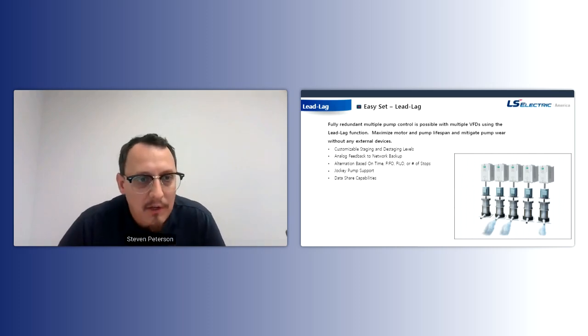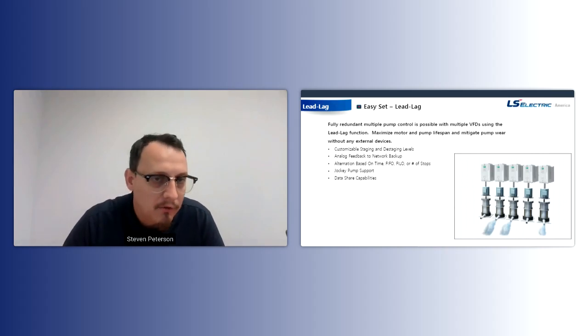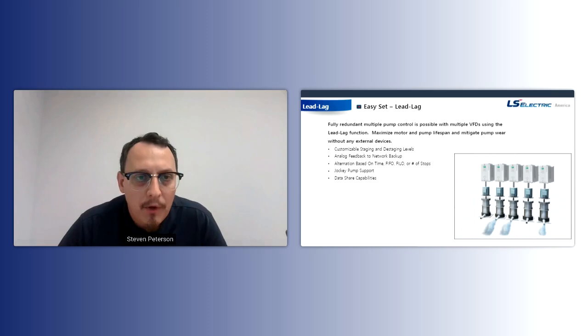So lead lag is essentially a fully redundant multiple pump control operation. This is possible via two different ways. You could do a simple contactor lag where you have one VFD where only one pump is variable speed, and then you're closing contactors for starting up the other pumps. What I focused on here is the level 2 lead lag, which is multiple drives and multiple pumps. This is an advantageous setup because you're maximizing motor and pump lifespan, and you're mitigating pump wear because you have things in place such as staging, destaging, and alternation.